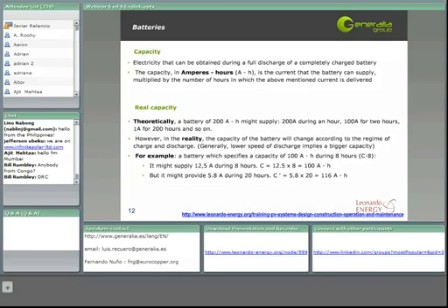So normally a good practice is to consider that if we discharge a battery for a longer period than the period specified in its data sheet, we can get more energy from the battery than the one that is specified.